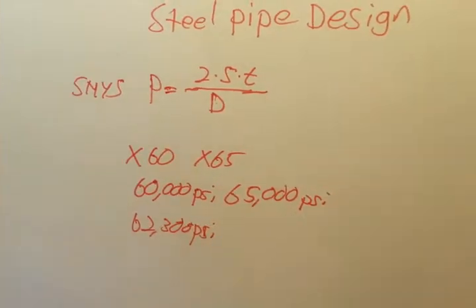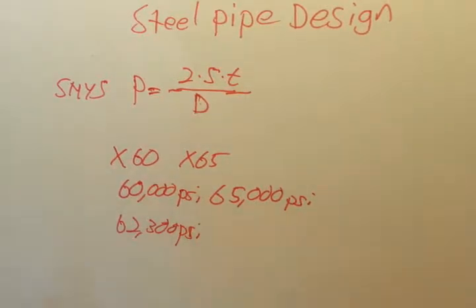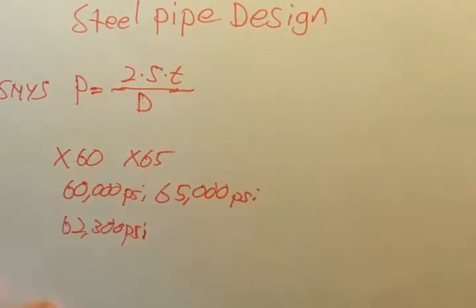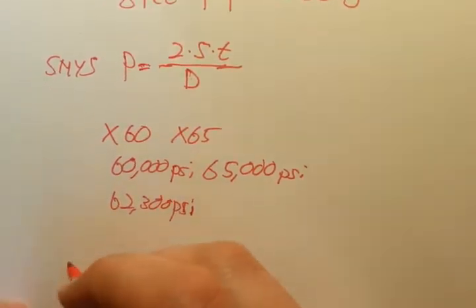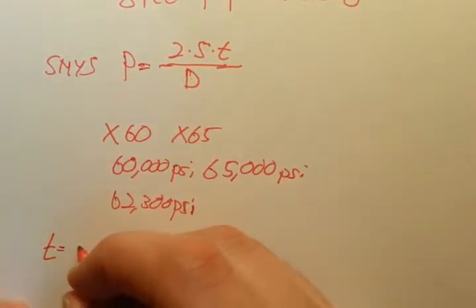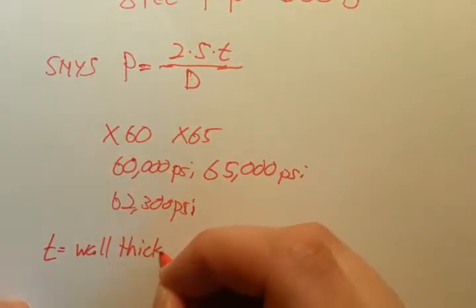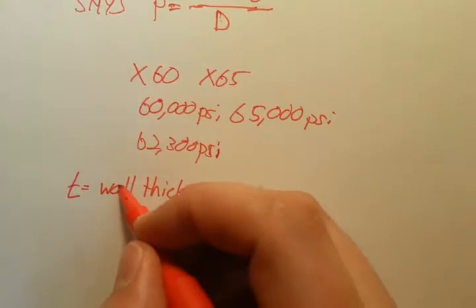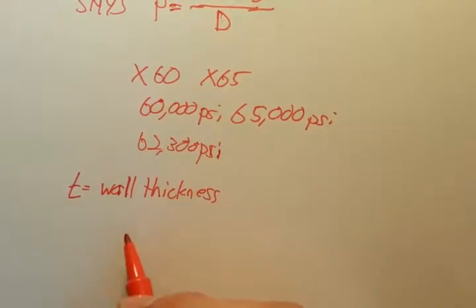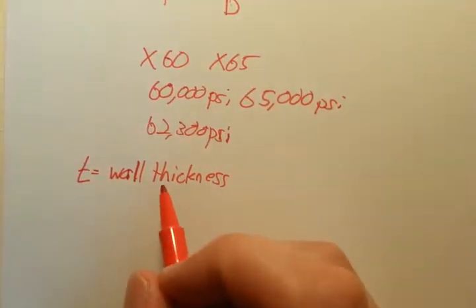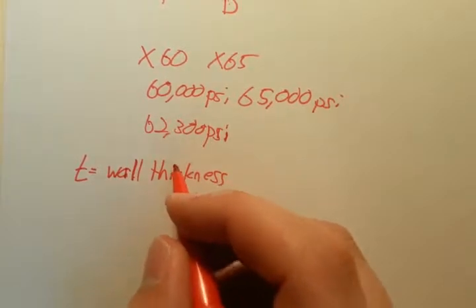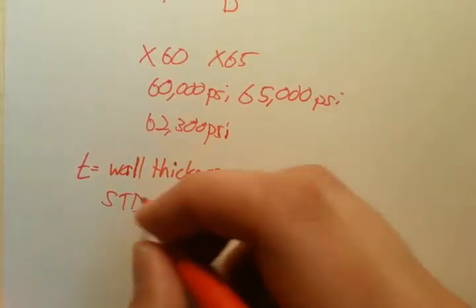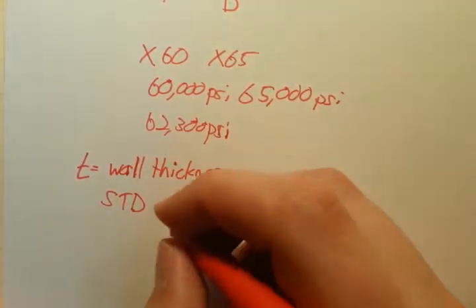Lowercase t, wall thickness, is standardized in the industry. To get that, you just go to what they call pipe charts, and they'll have corresponding outer diameters and sizes of pipe with wall thickness. A lot of people in shorthand will call it STD for standard wall thickness pipe, or SCH 80 for schedule 80, or SCH 40 for schedule 40.